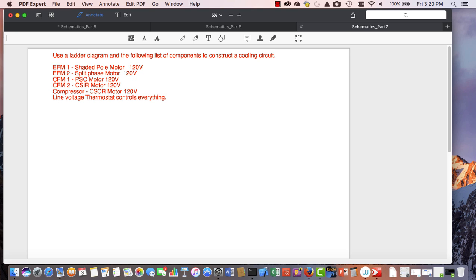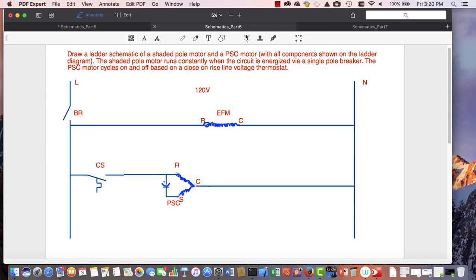We have a line voltage, everything in it is line voltage, and we're controlling different components with other line voltage components. So in the last schematic, we took an evaporator fan motor, which was a shaded pole, and we let it run constantly. Then we had a cooling thermostat controlling a PSC motor, and that PSC motor could be a compressor, could be condenser fan, could be a pump, could be anything, okay? But the purpose is we had one motor running constantly, and we had another motor controlled by a thermostat.